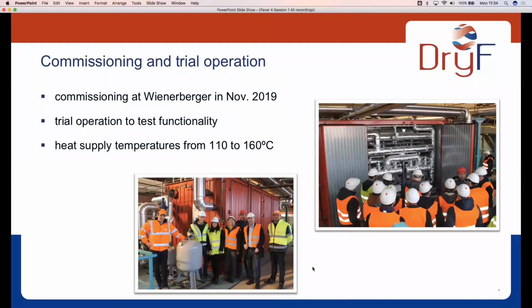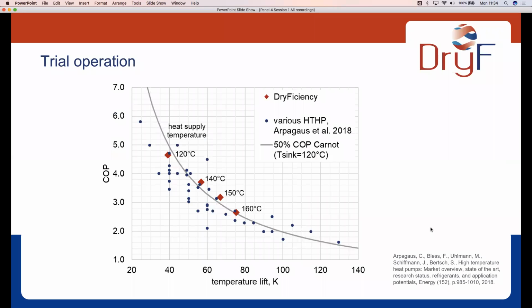We started the commissioning work in November last year, and then we did a rough trial operation to test the functionality of the heat pump, to test all the controls and really see how the heat pump behaves within the process. And within this trial operation, we tested different heat supply temperatures ranging from 110 to 160 degrees C. And in this diagram, that should come up right now, you see a summary of the trial operation.